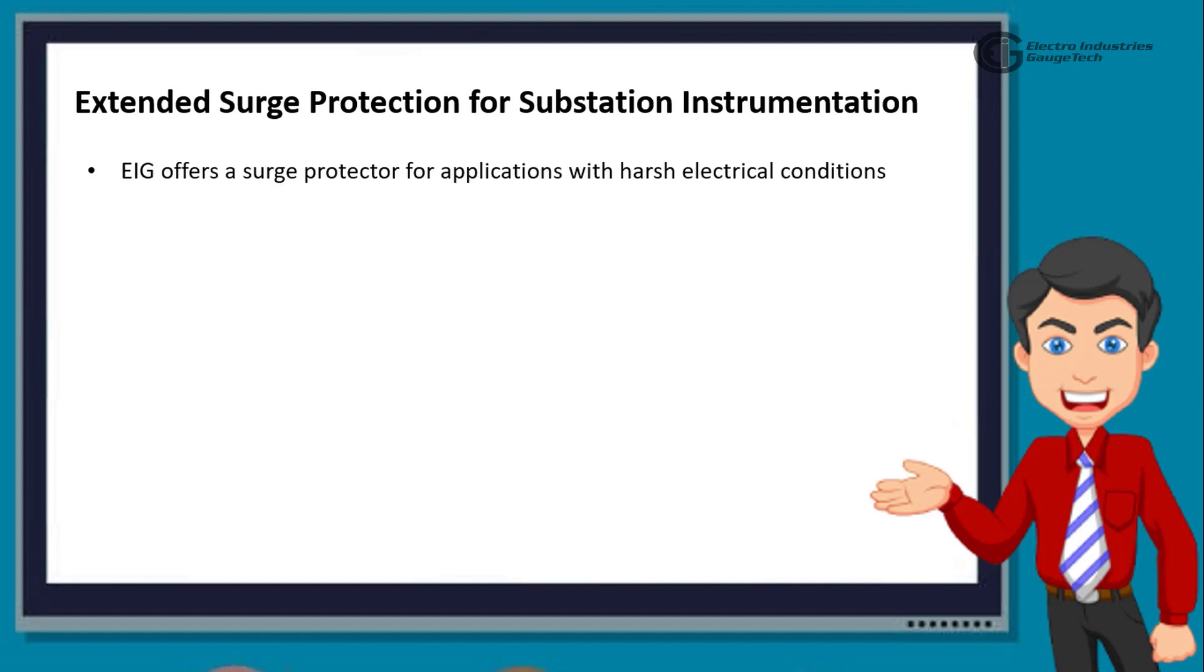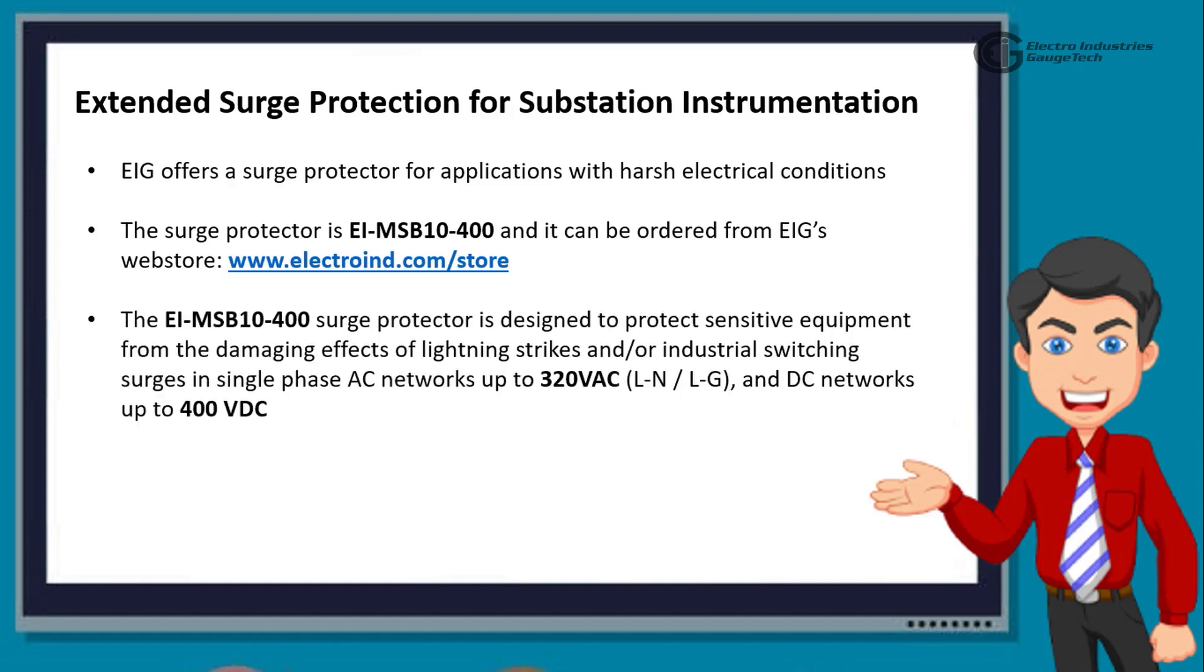Now, the last section to cover in this video is the extended surge protection for substation instrumentation. EIG offers a surge protector for applications with harsh electrical conditions. The surge protector is EI-MSB10-400, and it can be ordered from EIG's web store. The EI-MSB10-400 surge protector is designed to protect sensitive equipment from the damaging effects of lightning strikes, and/or industrial switching surges in single-phase AC networks up to 320 VACLN-LG, and DC networks up to 400 VDC. The protectors are ideal for metering systems, RTUs, PLCs, and protective relays.